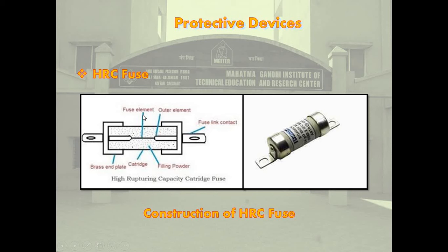Its advantages are the capability to clear high values of short circuit currents. They have high speed operation. They do not deteriorate with age over long periods. They require no maintenance. They provide reliable discrimination. They have an inverse time current characteristic. They are simple and easy to install.